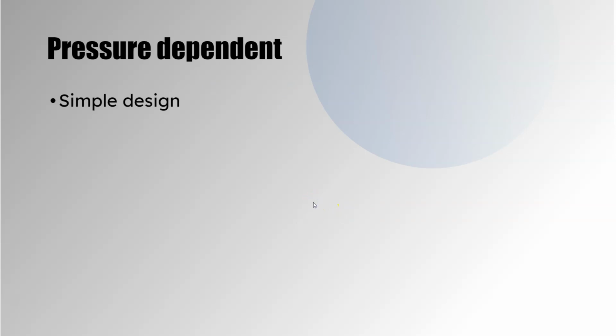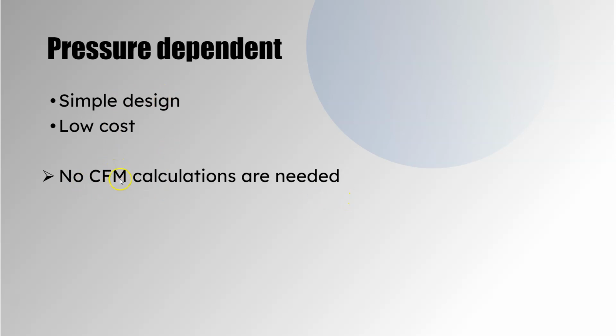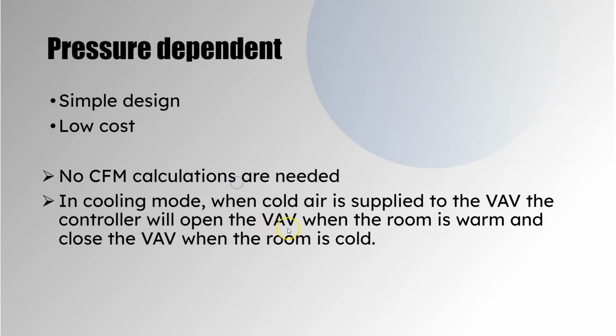Let's talk about pressure dependent. A pressure dependent is a very simple design and it's very cost effective, very low cost. Basically, with this kind of system, no CFM calculations are needed. So we could go back to that very first VAV box, the one that didn't have any flow tubes in it. That's all you need for a pressure dependent system. What it does is in cooling mode, when the space is warm, it opens up the VAV to put more cold air into the space. And when the room's cold, it closes off the VAV to put less air into the space. Now, we don't know how much air. That's the drawback of this one. So if your air handler's running super high speeds, you could be overcooling the space, putting a lot more air into the space than what it needs when it opens up.